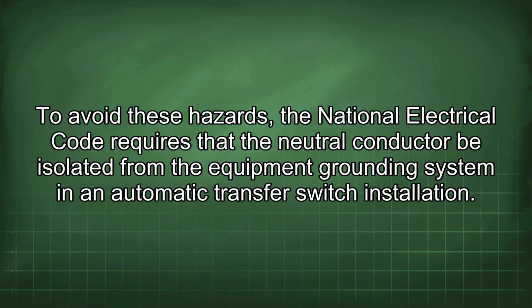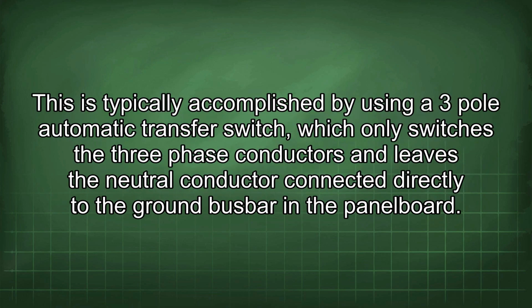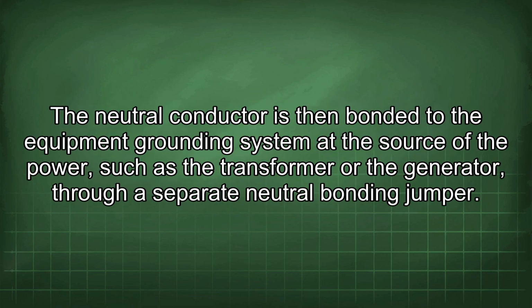To avoid these hazards, the National Electrical Code requires that the neutral conductor be isolated from the equipment grounding system in an automatic transfer switch installation. This is typically accomplished by using a 3-pole automatic transfer switch, which only switches the 3-phase conductors and leaves the neutral conductor connected directly to the ground busbar in the panel board. The neutral conductor is then bonded to the equipment grounding system at the source of the power, such as the transformer or the generator, through a separate neutral bonding jumper.